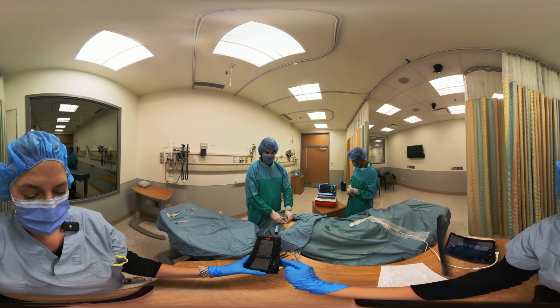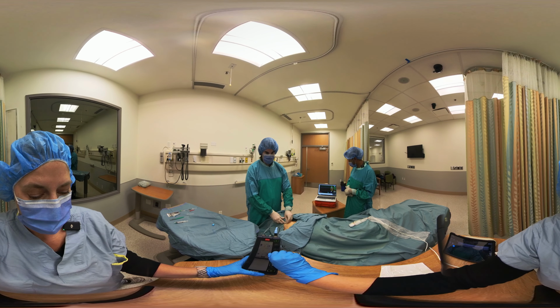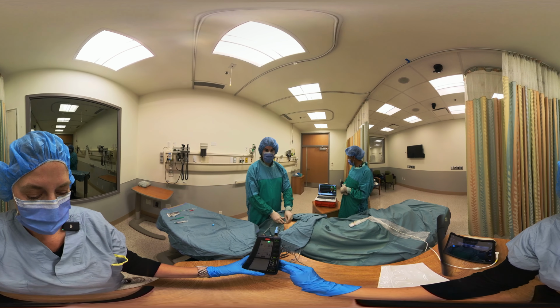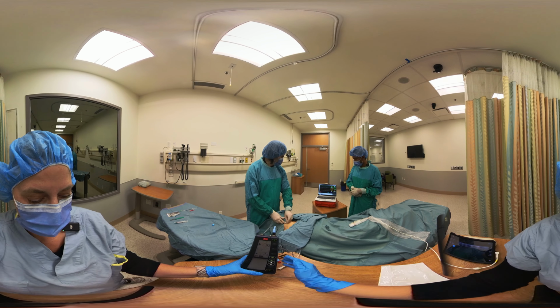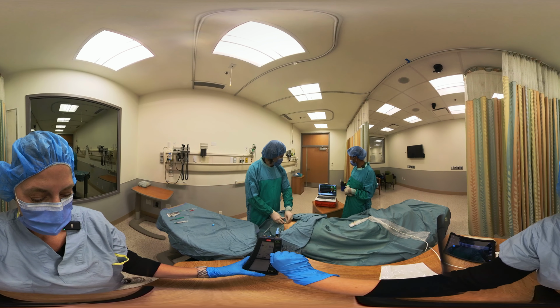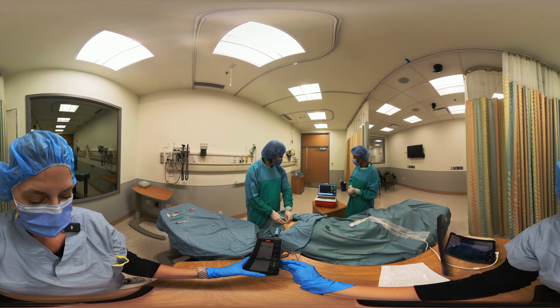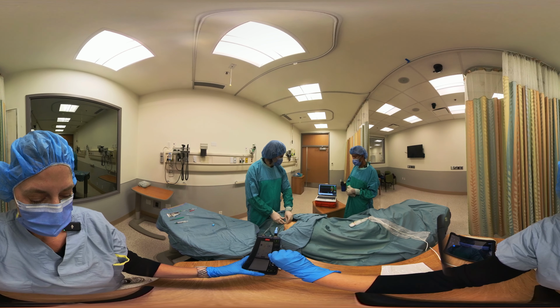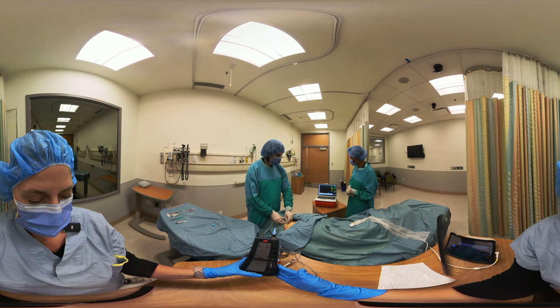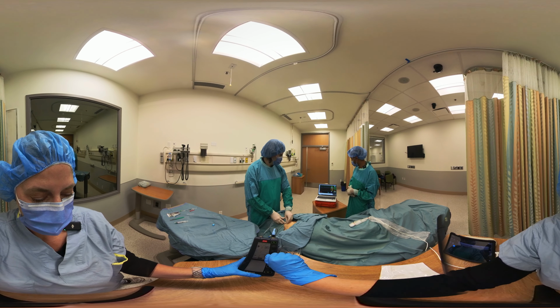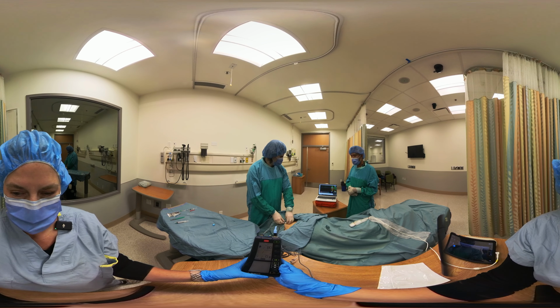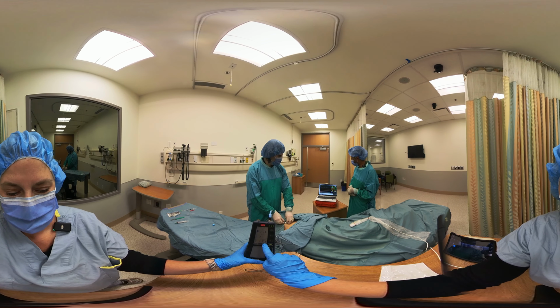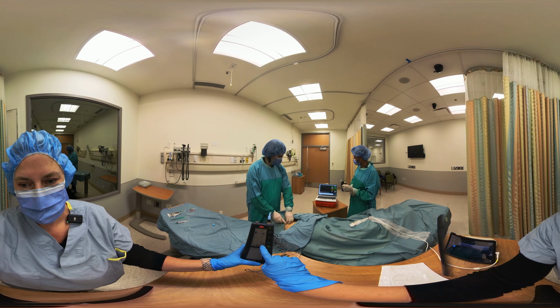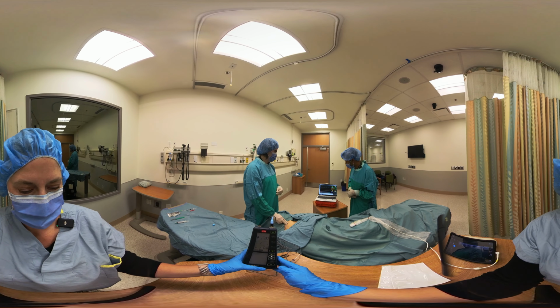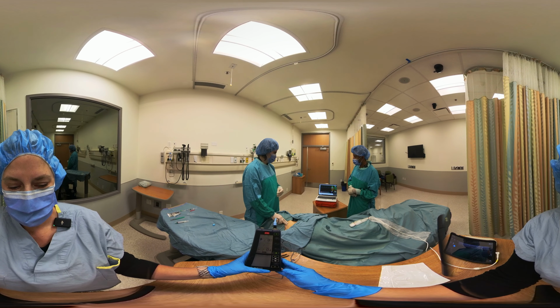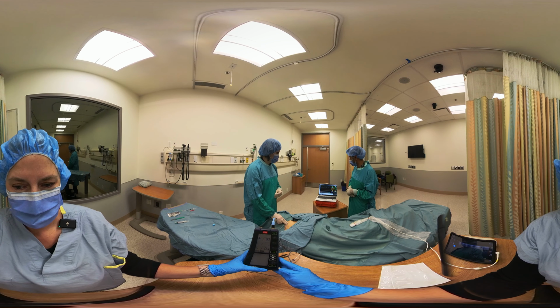So we'll go down by 1 millivolt after every 3 beats. So let's go to 4. Now let's go to 3 millivolts. Let's go to 2 millivolts. Let's go to 1.5 millivolts. Let's go to 1 millivolt, and as you can see, we still have pacing, which means we're capturing. Let's go to 0.8 millivolts. And as you can see, at 0.8 millivolts, we have had a change in rhythm, which means that we're no longer capturing. We will now increase the threshold back up to typically 3 times the threshold.